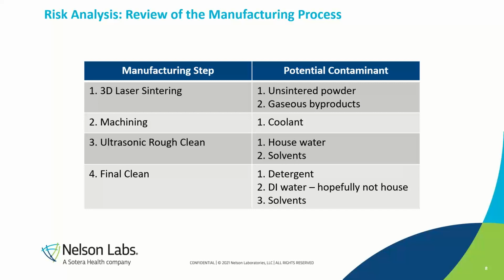Machining, that could mean a variety of things, and it could introduce a variety of potential contaminants: coolants, lubricants, acids, all types of things. You might have an in-process clean with possibly house or city feed water. Ideally not, but maybe. You might have more aggressive cleaning agents at this stage, and solvents, degreasers, that type of thing, all kinds of variety as well. And then a final clean, again, possibly more detergents and cleaning agents, hopefully DI water at this phase, but maybe not. Maybe there's city feed water at this phase, and maybe a solvent rinse like IPA, that's possible.